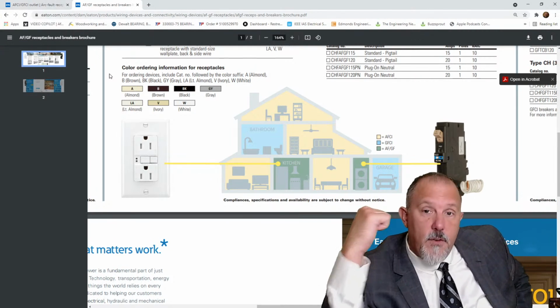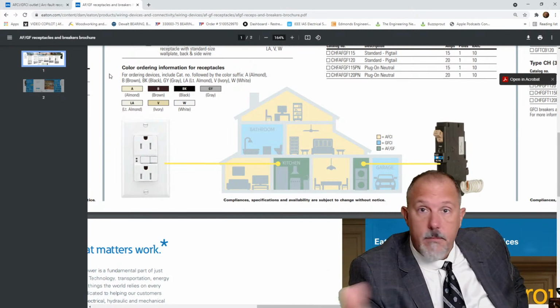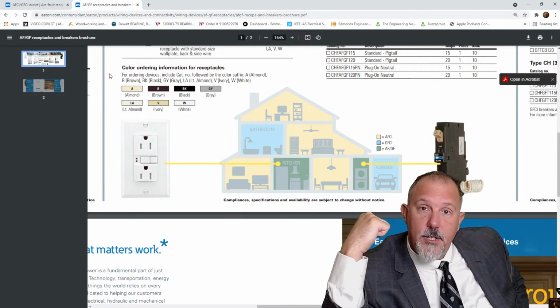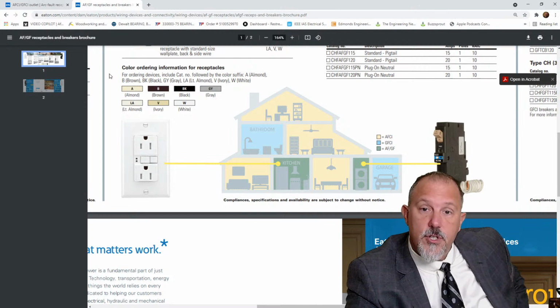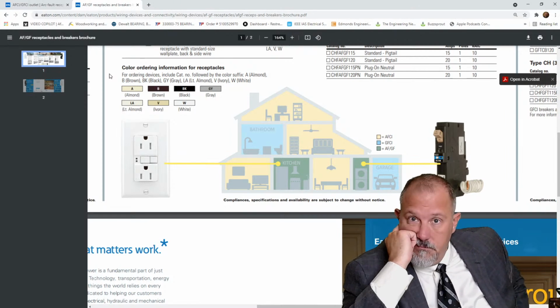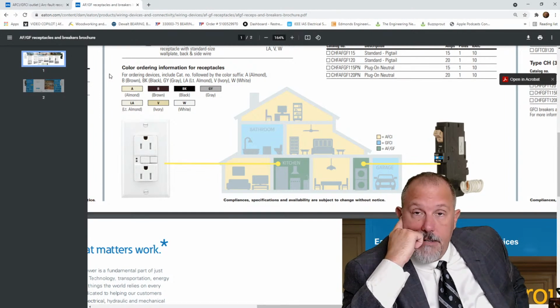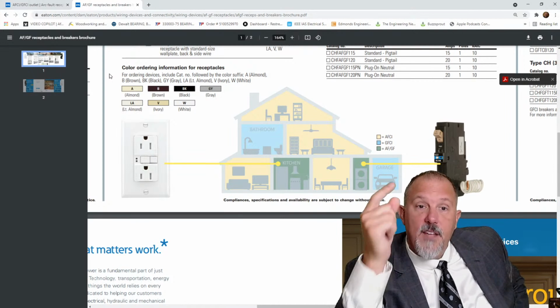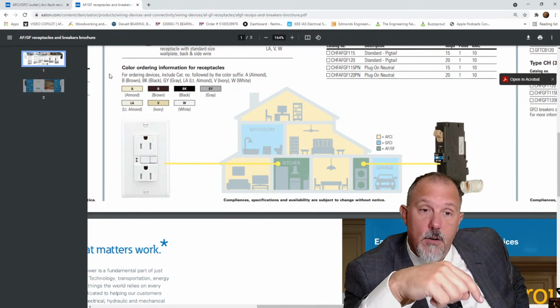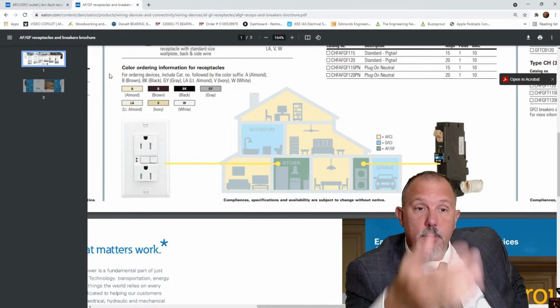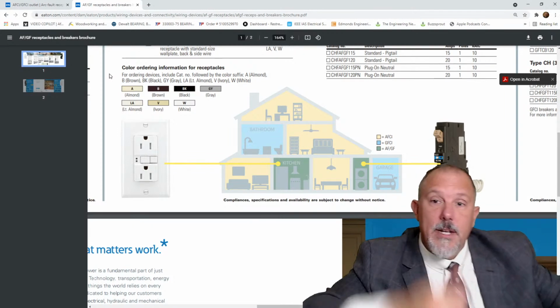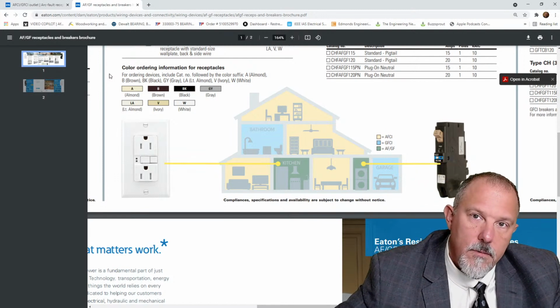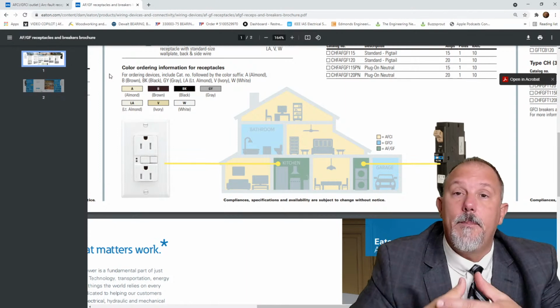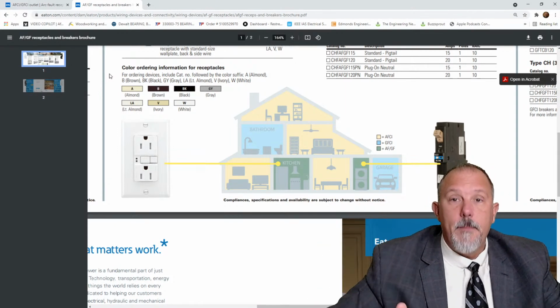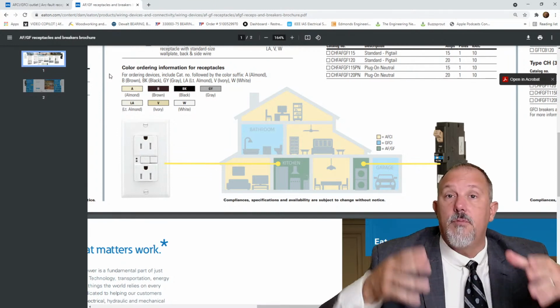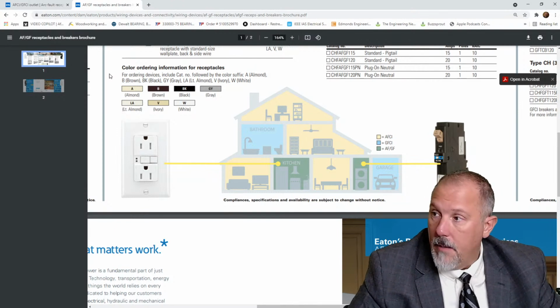Or you can just do an arc fault breaker and a ground fault receptacle. That's an option too. So you can put an arc fault breaker protecting the entire branch circuit and connected cords, and then you put a ground fault circuit interrupter receptacle that serves the loads. That's perfectly viable to do. You can put AF/GF in the breaker. If you protect that home run circuit and follow the rules in 210.12 and you can provide an OBC AFCI downstream, you can put an AFCI GFCI receptacle. You could put an AFCI breaker and an AF/GF receptacle. You're double dutying the arc fault, but there's no compatibility issues between arc fault and ground fault. There's no compatibility issues between any of these technologies. So they can both reside on the exact same branch circuit. No problems with that.